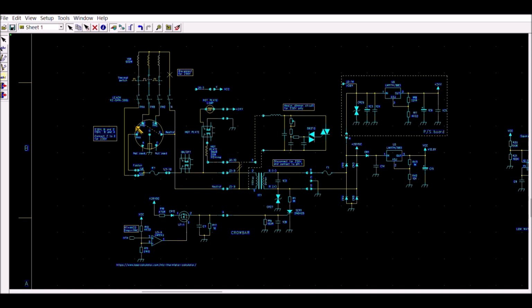We need to connect 115 volts between the neutral here and phase A, which is terminal B of the circular connector. The power will be 900 watts. If you want 1800 watts, you can connect terminals B and C together. For this voltage, 115 volts, the only thing to change is the transformer. It is possible to replace the transformer by an AC to DC converter. I have estimated the power at approximately 20 watts.